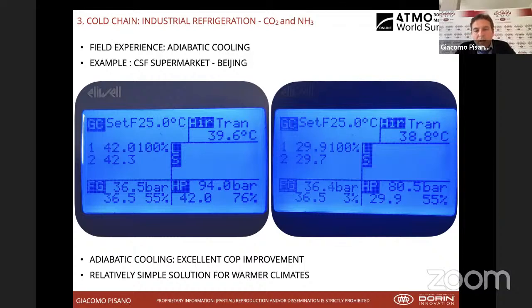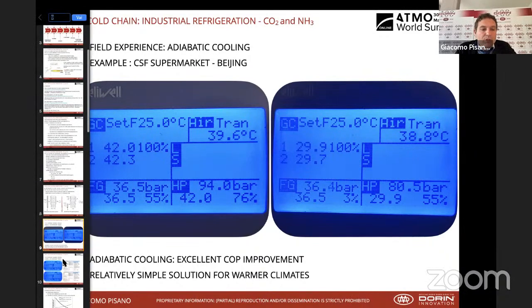76%. The next week, the adiabatic gas cooler pads were put into operation. So you can still see very high ambient temperature, 38.8. But look at the head pressure. From 94 bar, we went down to 80.5 bar with a gas cooler outlet temperature of 30 degrees C and the closing of the high pressure valve of 55%. So on a very warm day, in a dry environment, adiabatic cooling with CO2 works extremely well, because it enables you to provide a significant COP boost.